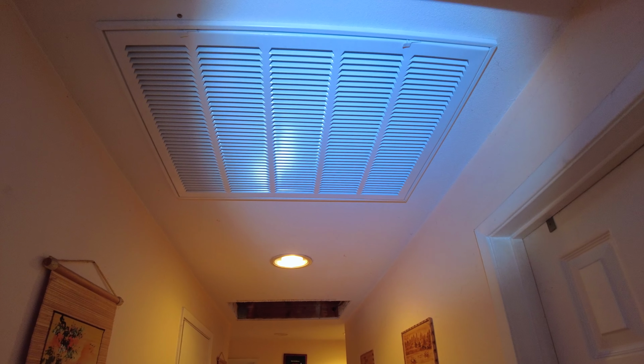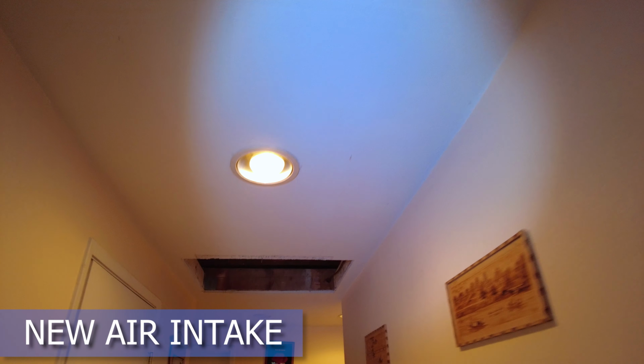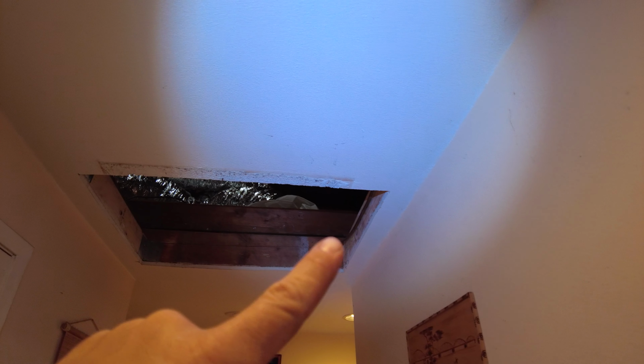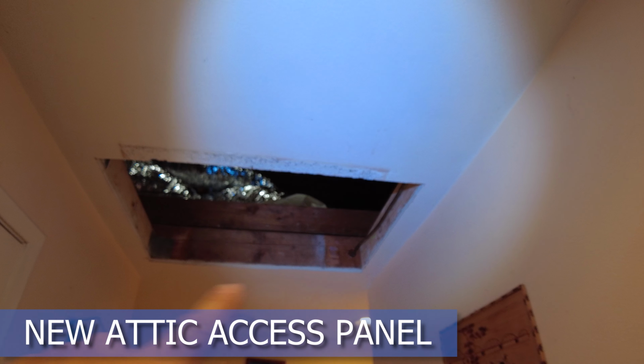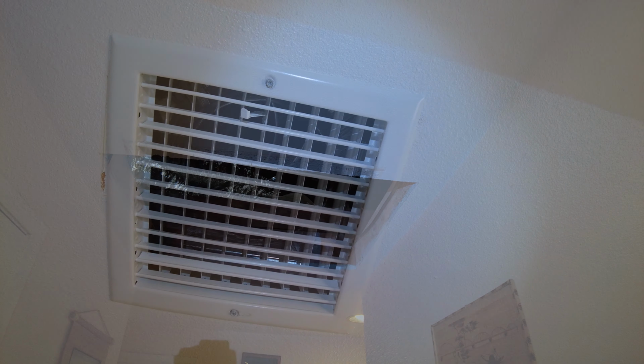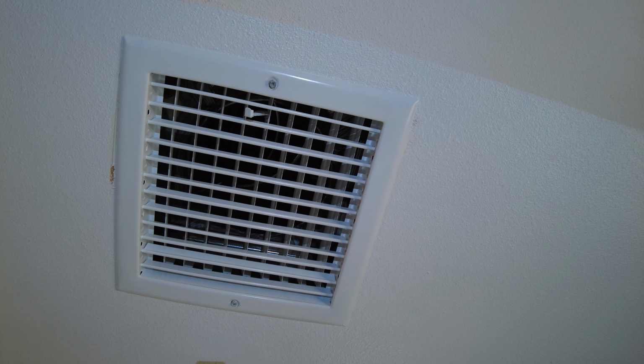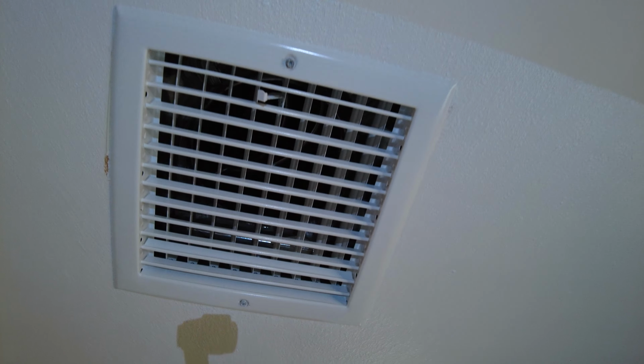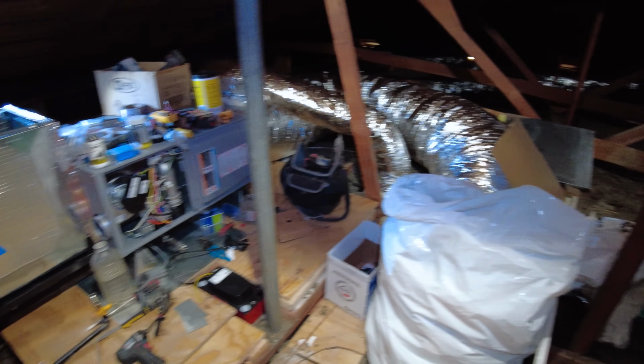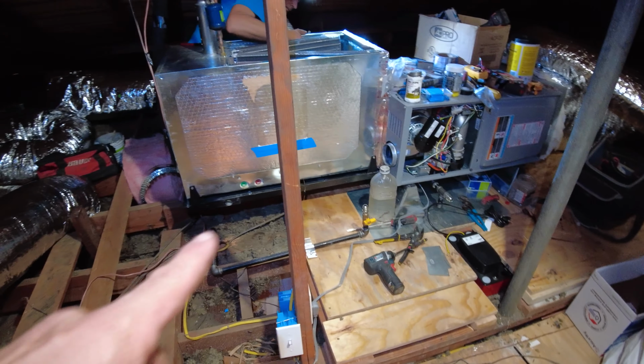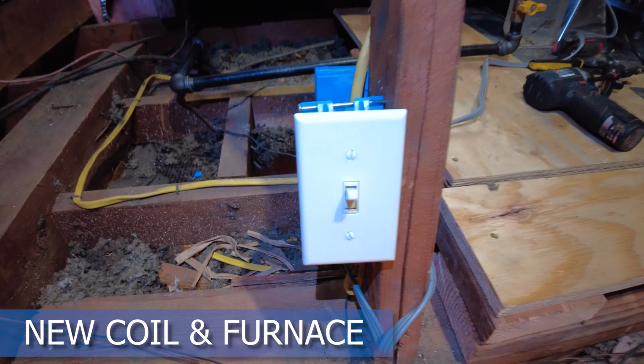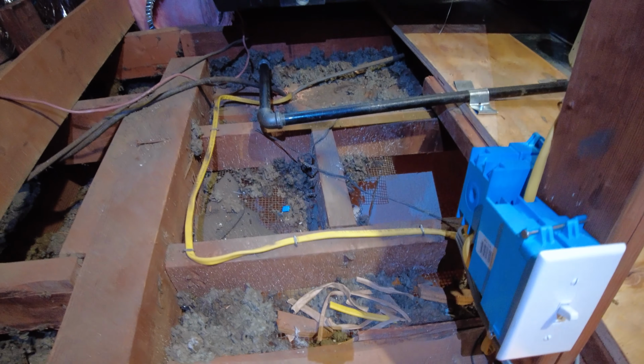As you can see, we added a new air intake, and there's going to be a new attic access panel. We already enlarged the opening and framed around it. We enlarged the supply vent in the kitchen. It's a bar type, high efficiency register. So this is our work in progress. New coil, new furnace. We already did the electrical and extended the gas line from the bottom.